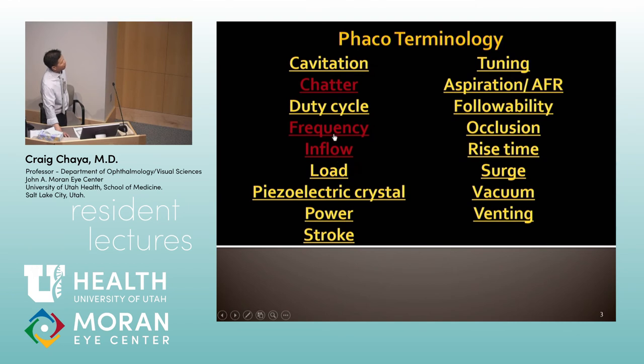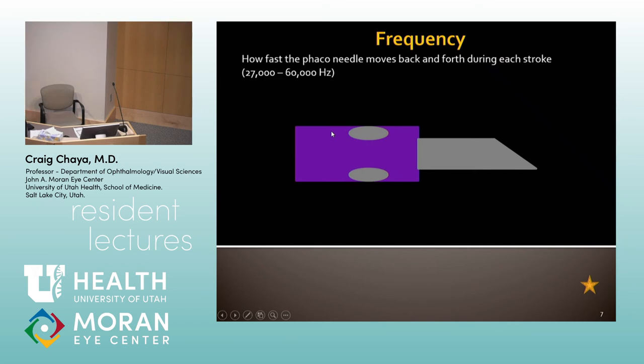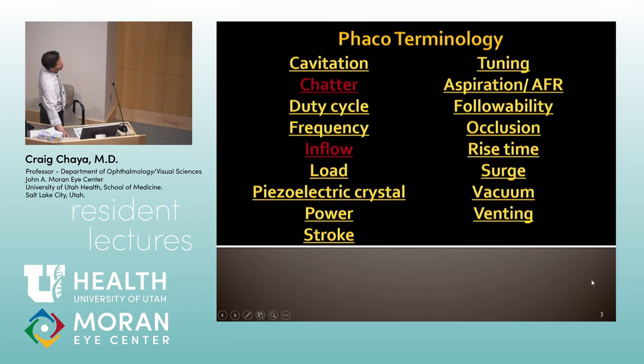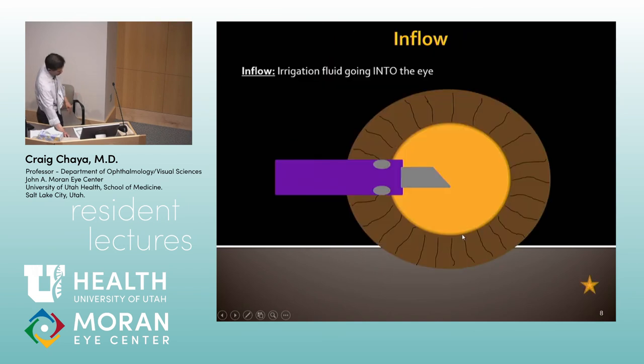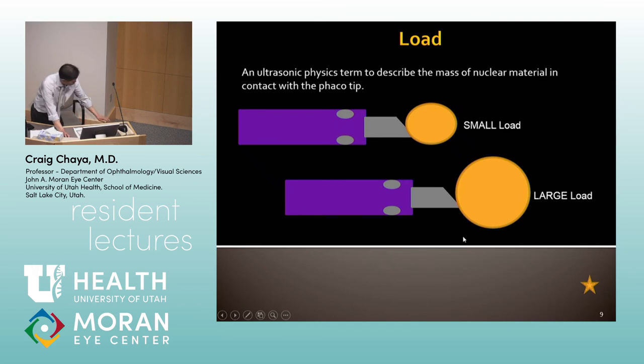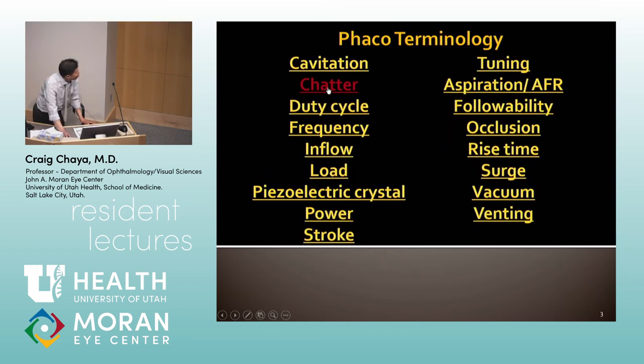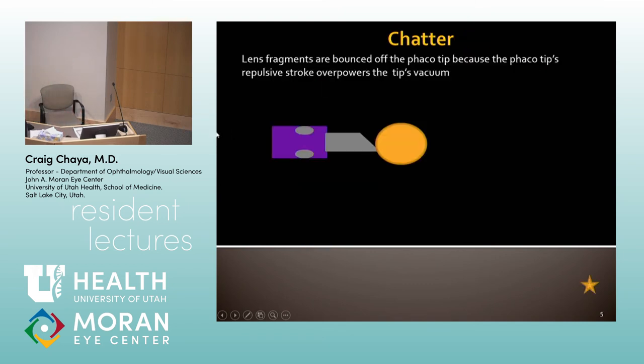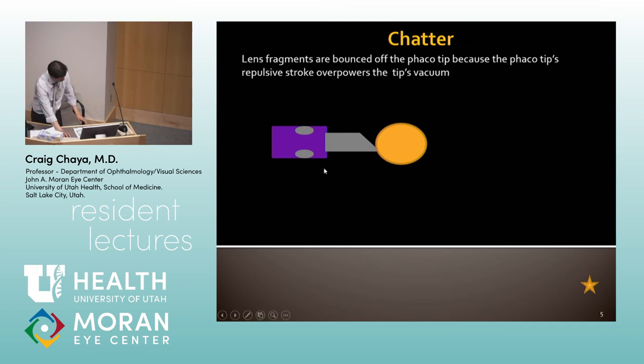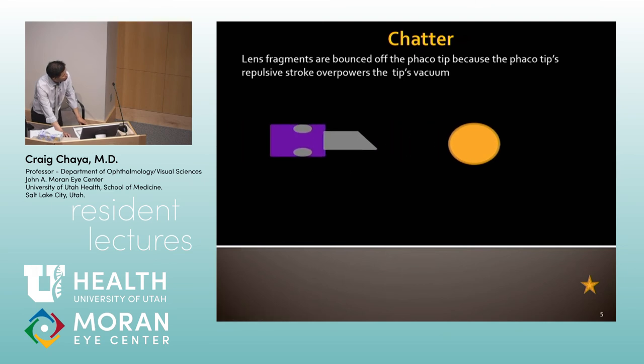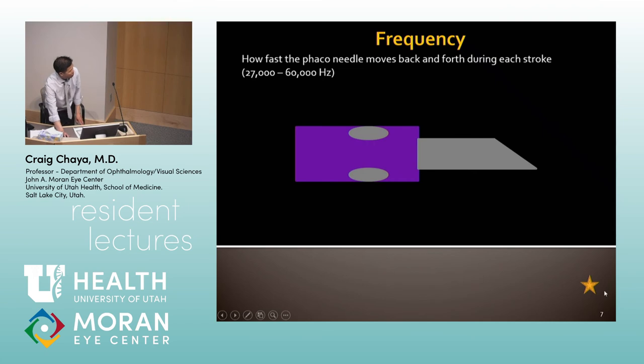Vibration frequency is just the rate at which the phaco needle moves back and forth — somewhere between 27,000 and 60,000 hertz, or kilohertz range. Inflow is just irrigation flow going into the eye. Chatter is important: lens fragments are repelled off the tip. We don't want chatter — it makes things less efficient, and you've got pieces down in the angle, sulcus, or bag, not staying at your tip. Needle moves, boom, pieces go away — we don't want that chatter during surgery.